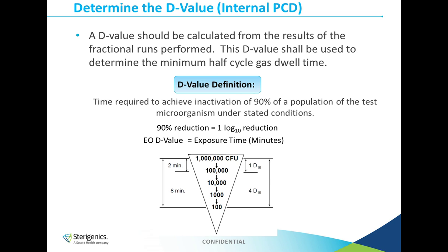If you have your internal PCD and you put it into a process that has a processing temperature of, let's say, 100 degrees, and then you take that PCD, the exact same one, and you put it into a sterilization process that has a temperature set point of 130, you're going to get different results. So you're going to get different D values. So remember, as you adjust those parameters, you're going to see variances in your D value.